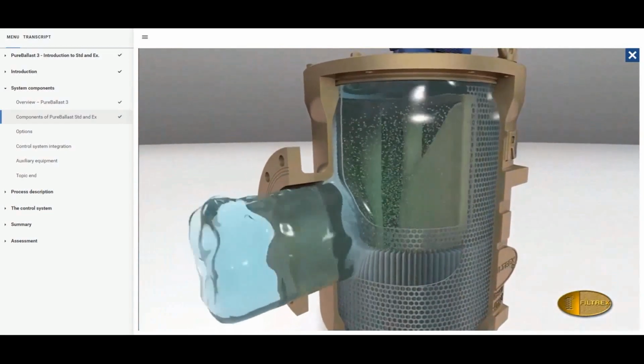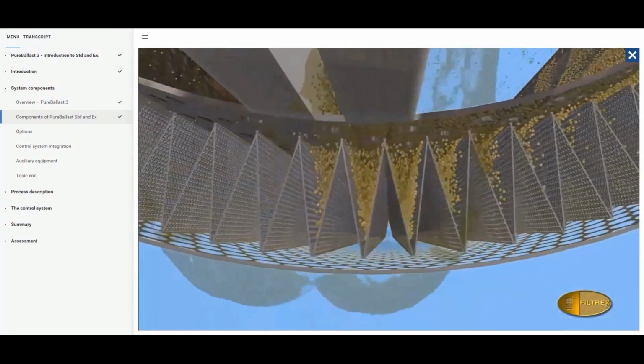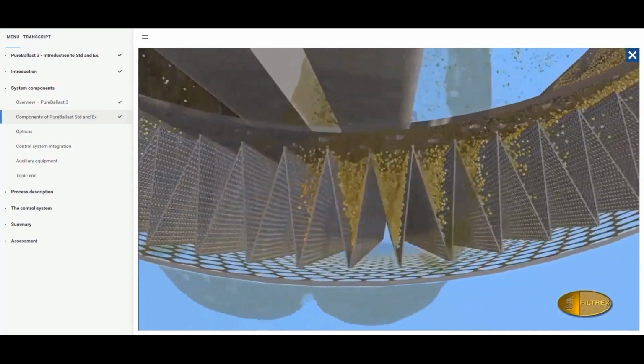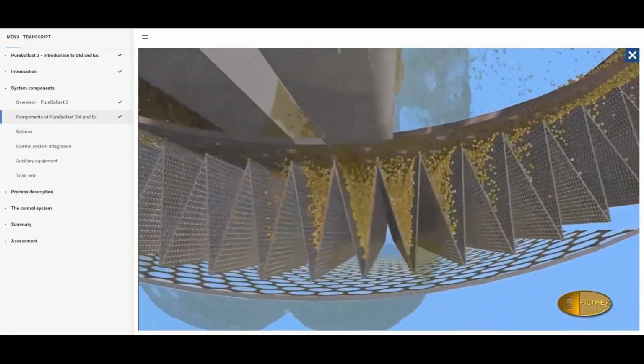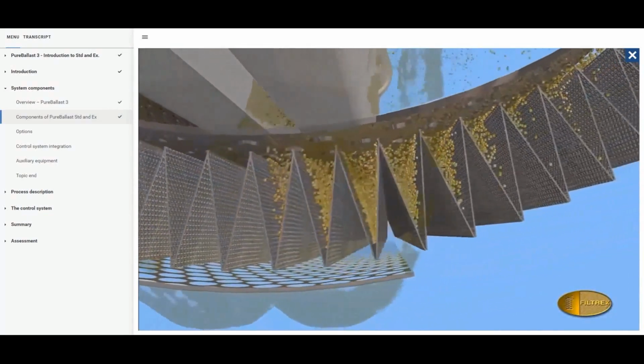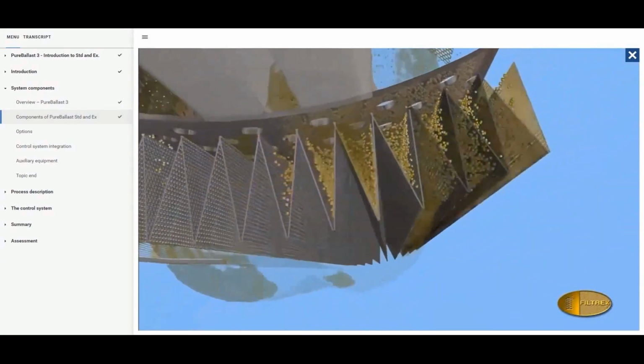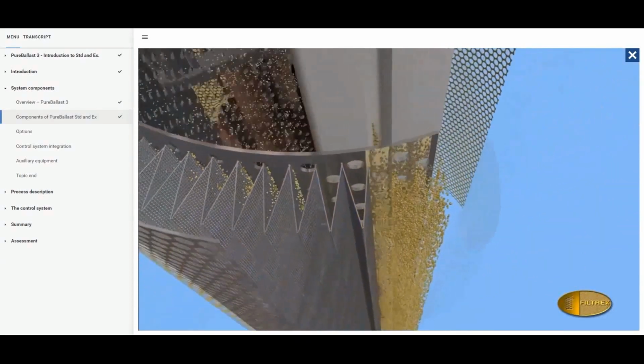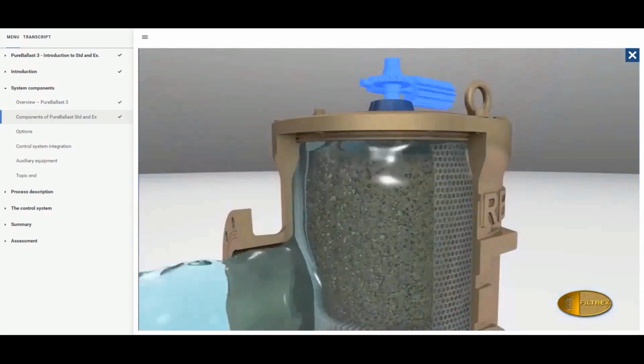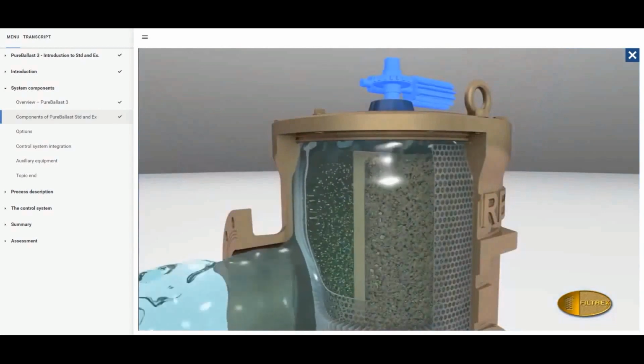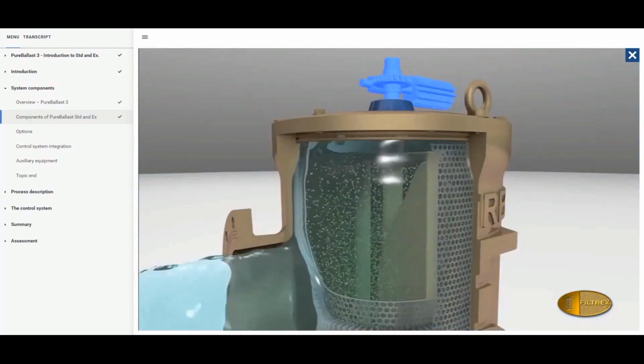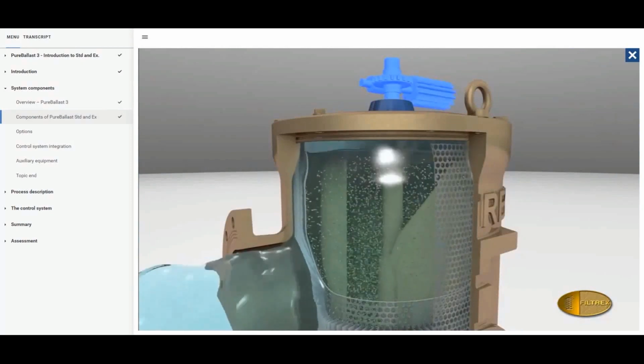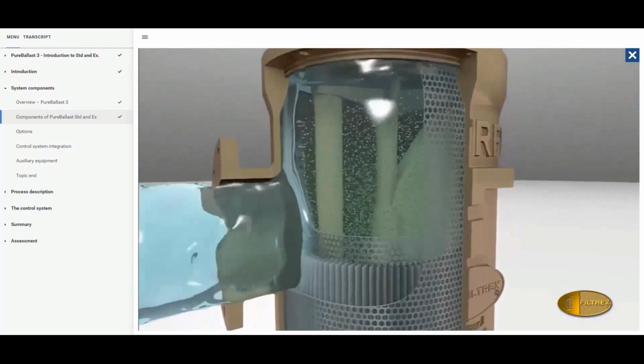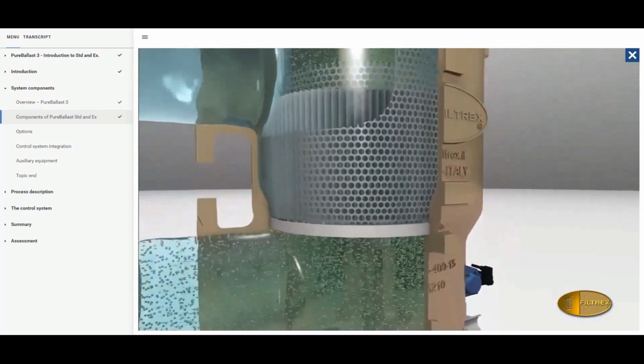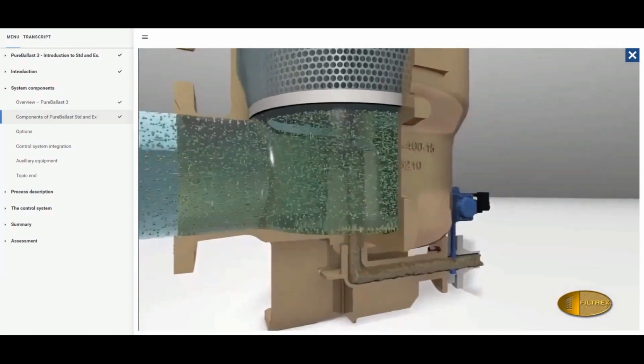While all sectors of the filter element ensure the normal filtration from inside to outside of the filtering element, the sectors in front of the rotating nozzle are rapidly cleaned one by one, with a reverse flow drawn from outside to inside of the filtering element. Thanks to the suction effect generated, the impurities are transported by the flow in the backwash line through the sludge duct and the backwash valve for disposal.